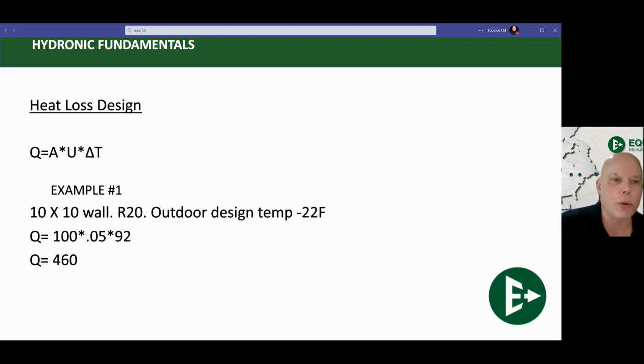So let's just break one down and do an example. Q equals A times U times delta T. A 10 by 10 wall with R20 insulation and an outdoor design temperature of minus 22 Fahrenheit, which is extremely cold. It's like Hudson's Bay area or up in Nunavut or Northwest Territories. That's where you're going to have outdoor design temperatures of that cold. So let's do the math. A 10 by 10 wall has an area of 100, that's 100 square feet. Then you have R20. In order to find your U value, it is 1 divided by R. So U value is 1 divided by 20, which is 0.05.